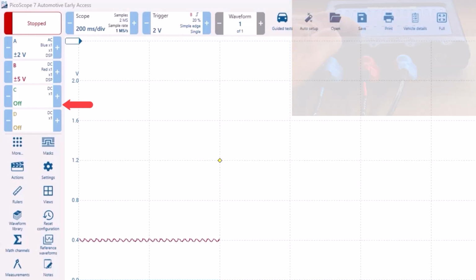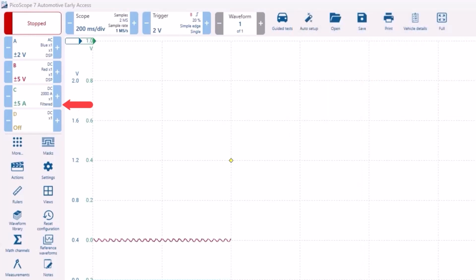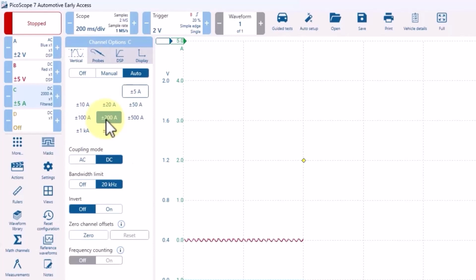However, I still need to configure it. Set the amperage to plus or minus 200 amps. Notice the bandwidth limit is active at 20,000 Hz. This is recommended and will help remove excessive noise often associated with inductive amp clamps.